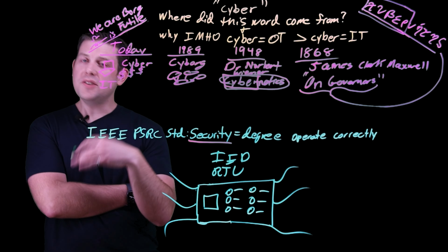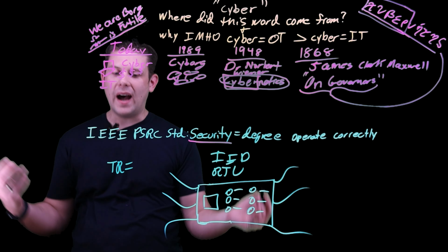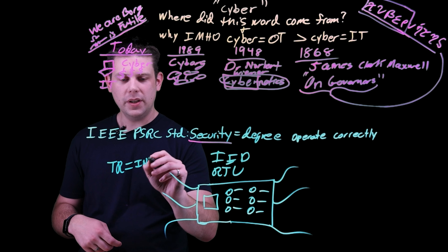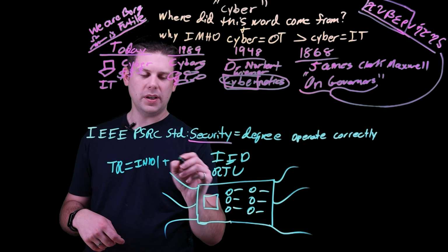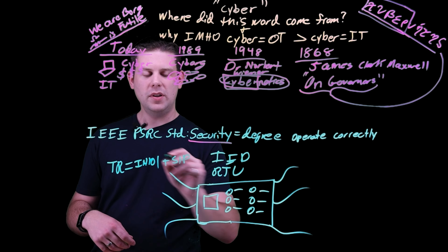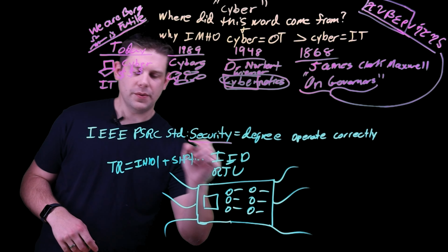Inside of this device is a different programming language, but you can actually create logic. You say, all right, relay, I want you to trip if an input is high plus another input. Let's say there's a fault, a 51 overcurrent on a phase, plus something else.